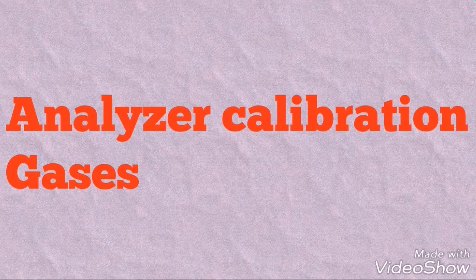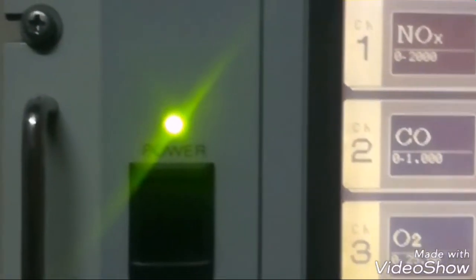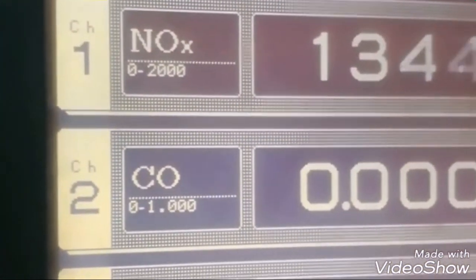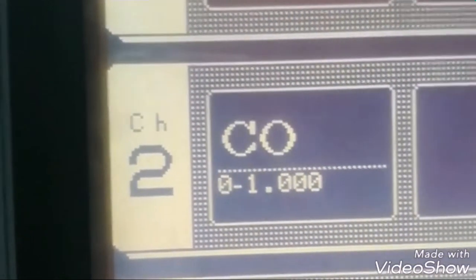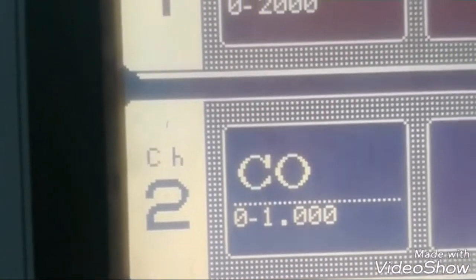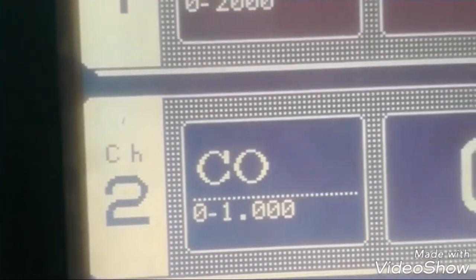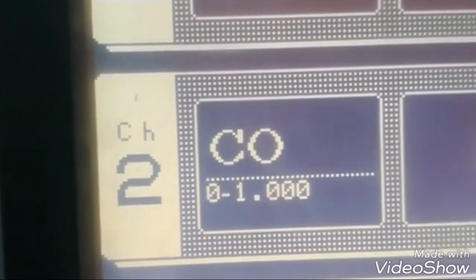Hello friends, how are you? Today I will tell you about the analyzer calibration gases. Here you can see the display of the analyzer. You are seeing the range. Range of NOx is 0 to 2000 ppm (parts per million). Range of CO is 0 to 1% volume percent. And the third gas is O2 and its range is 0 to 25%.